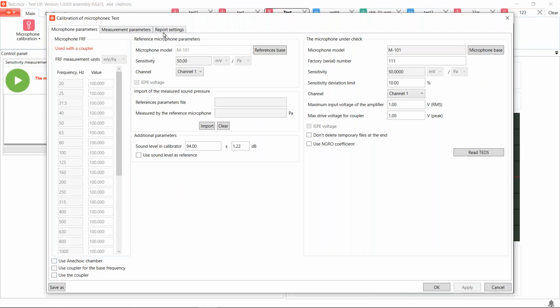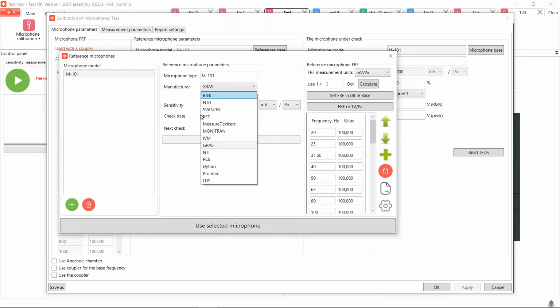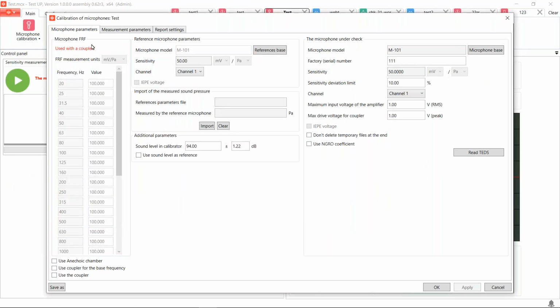Next, we are to look at the reference microphone parameters. So we have the base of references. Here you can choose the manufacturer of your microphone and the microphone type. You are to specify if IEPE voltage is applied, the sensitivity of the microphone, the date of the calibration check, and the date of the next check. And here I also wanted to pay your attention that the reference microphone FRF panel allows you to set the dependence of the microphone sensitivity from frequency. So you can see it on the left in this window. And in this table, you can fill the FRF.